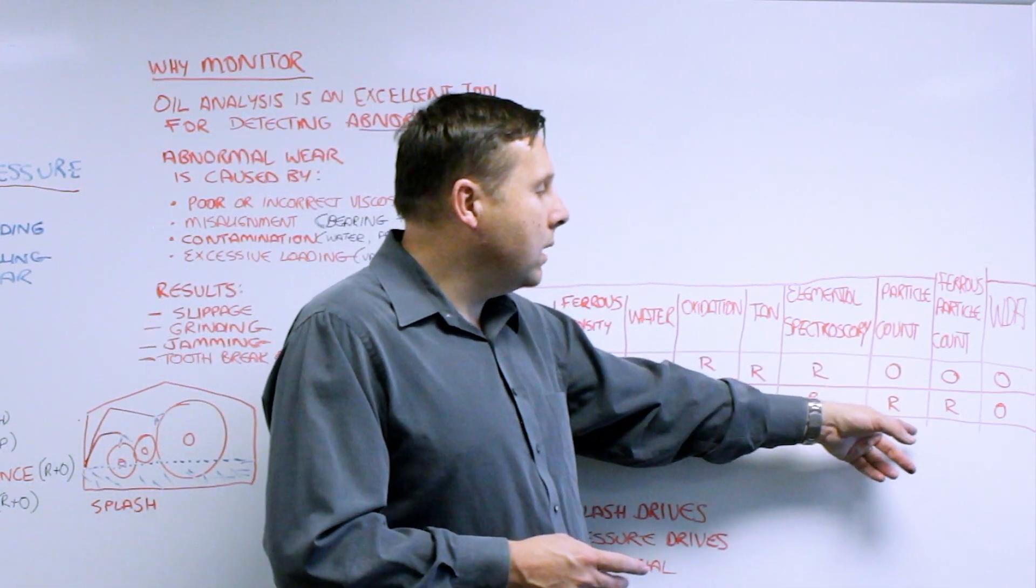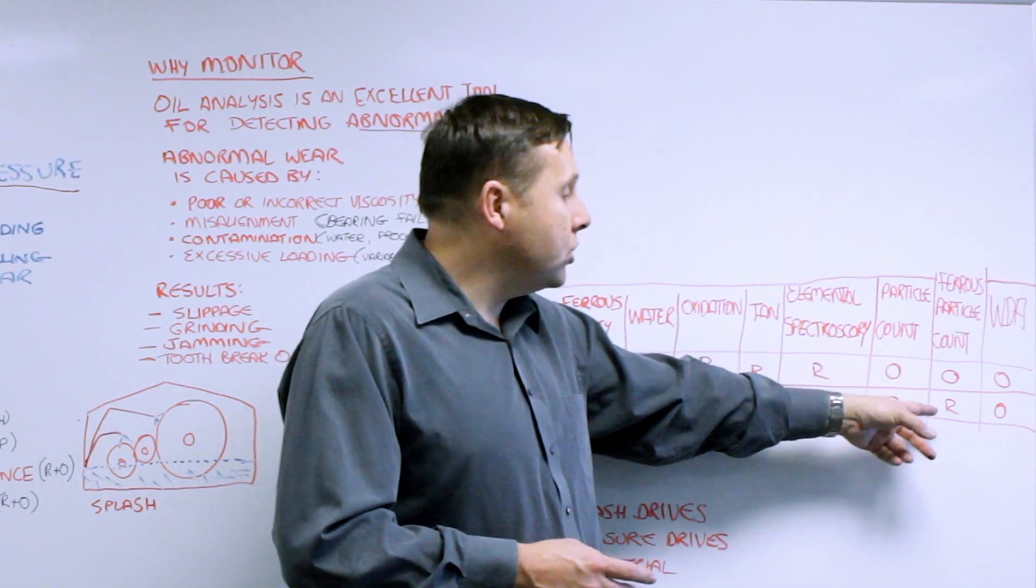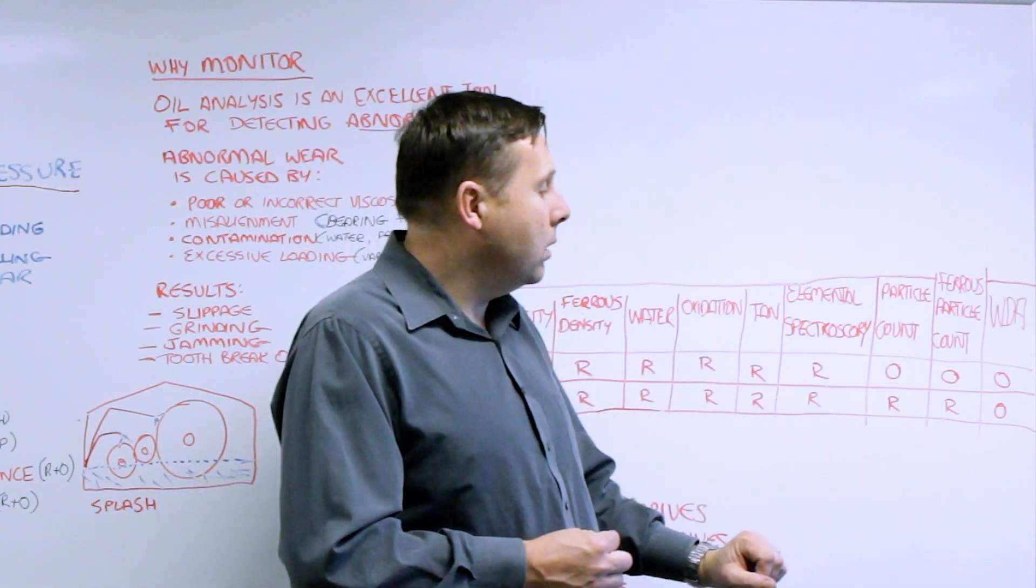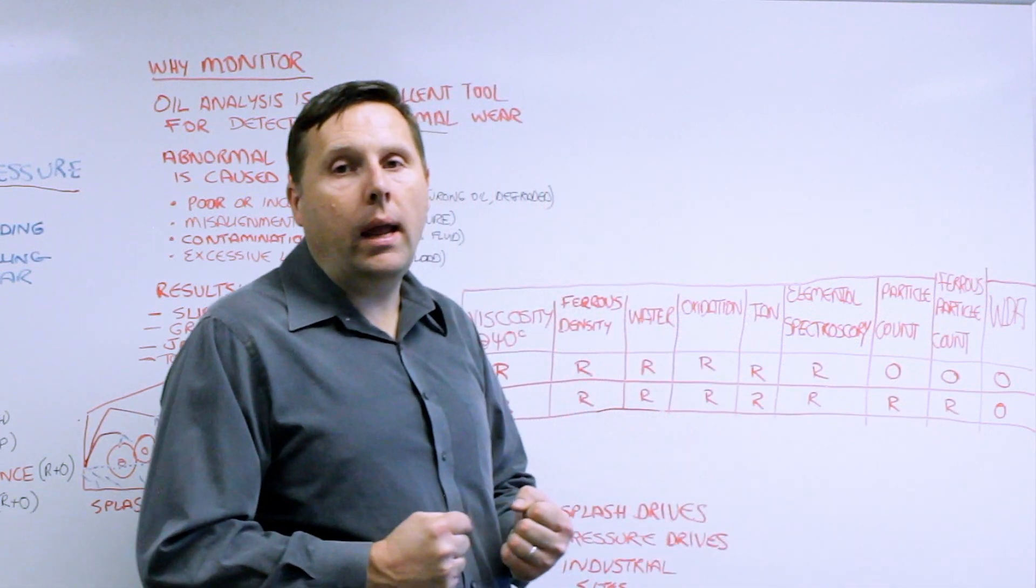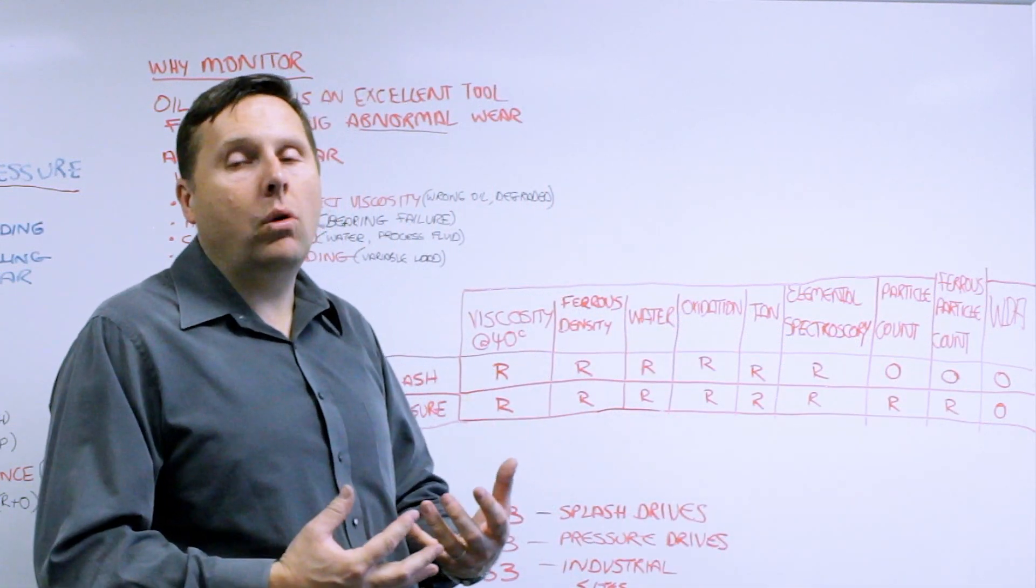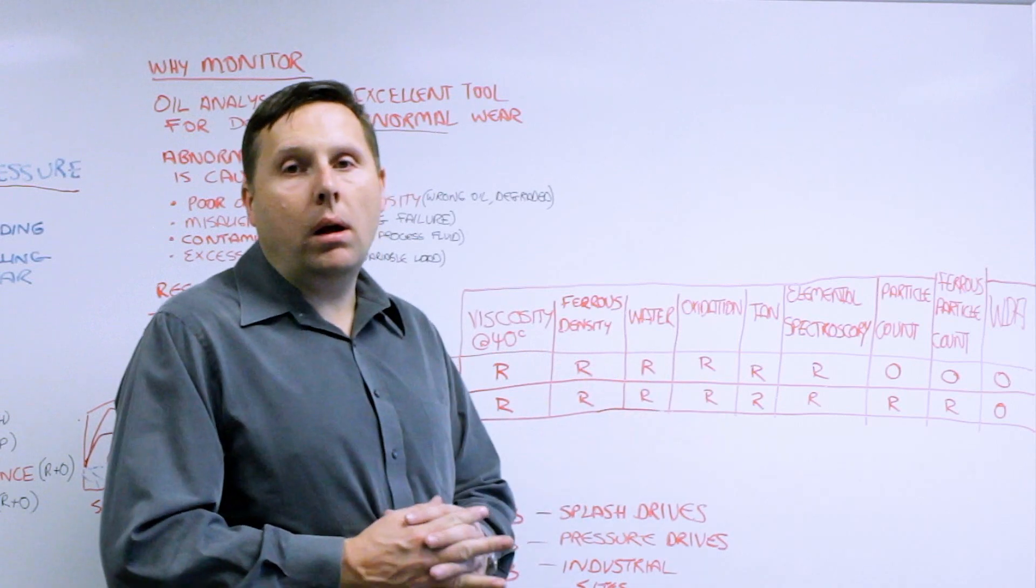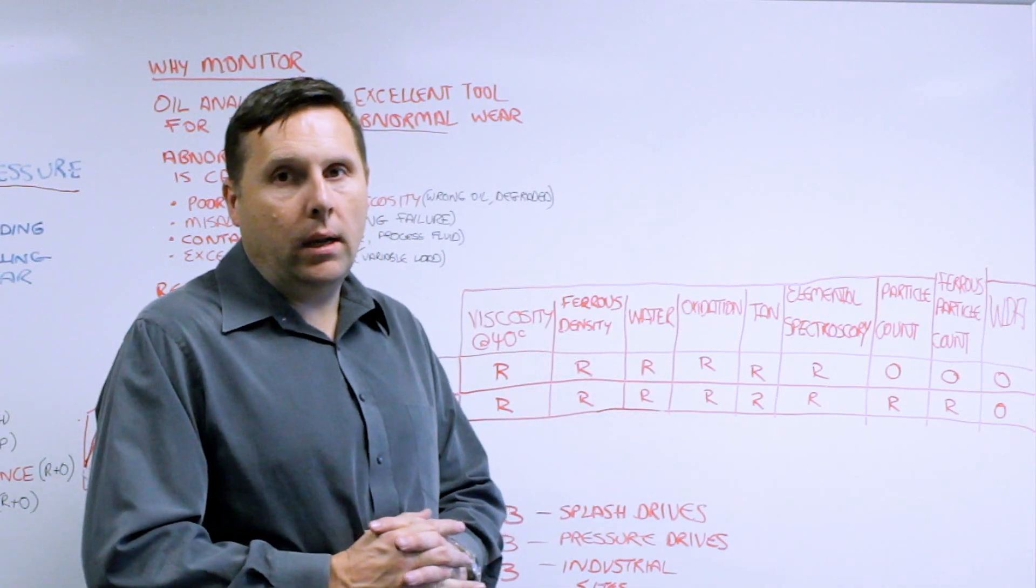And finally ferrous particle count optional on splash, recommended for pressure systems, and wear debris analysis or WDA should be an optional requirement when you identify a problem occurring and you want to do root cause diagnostics.